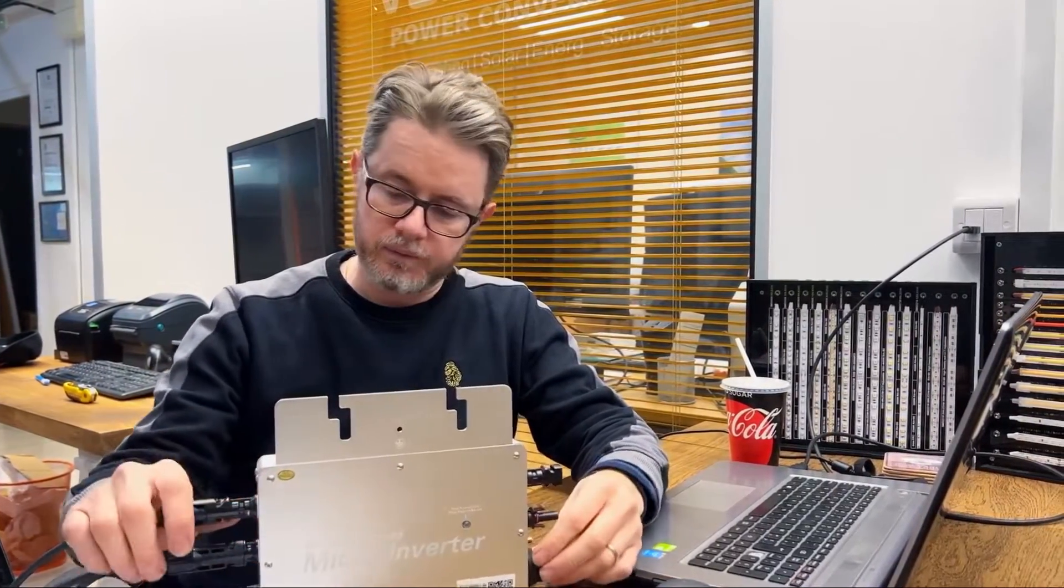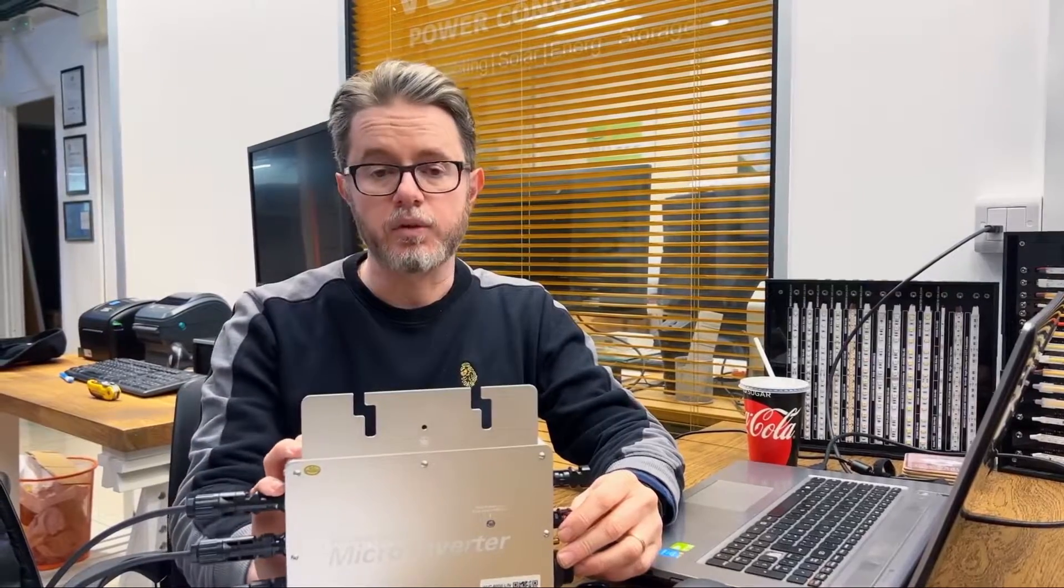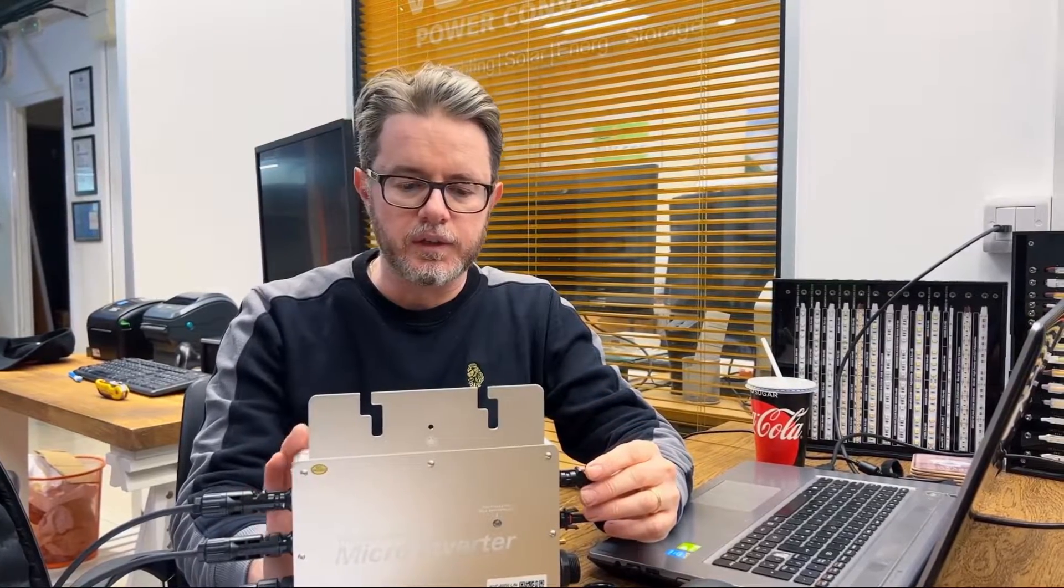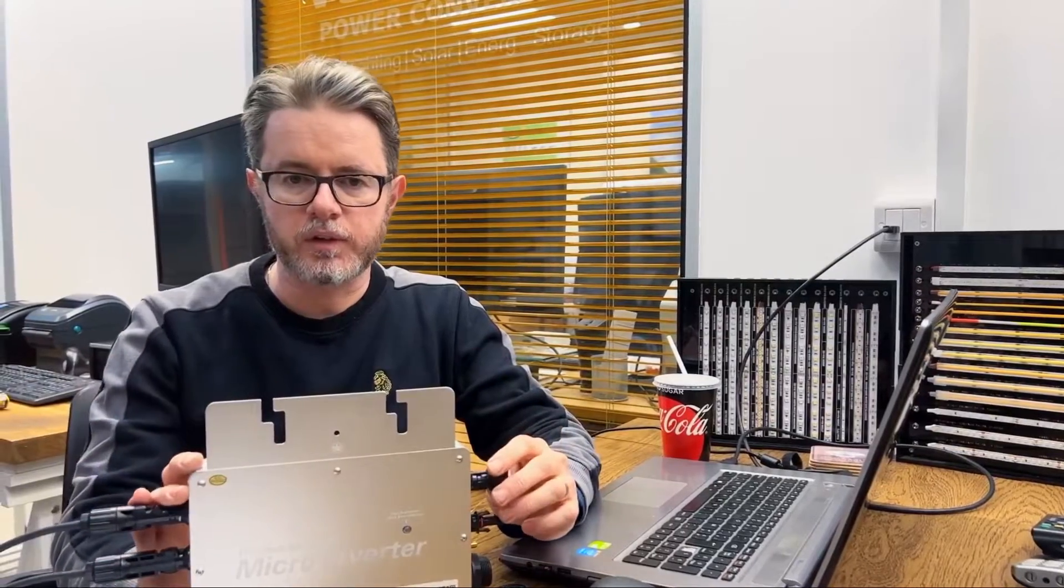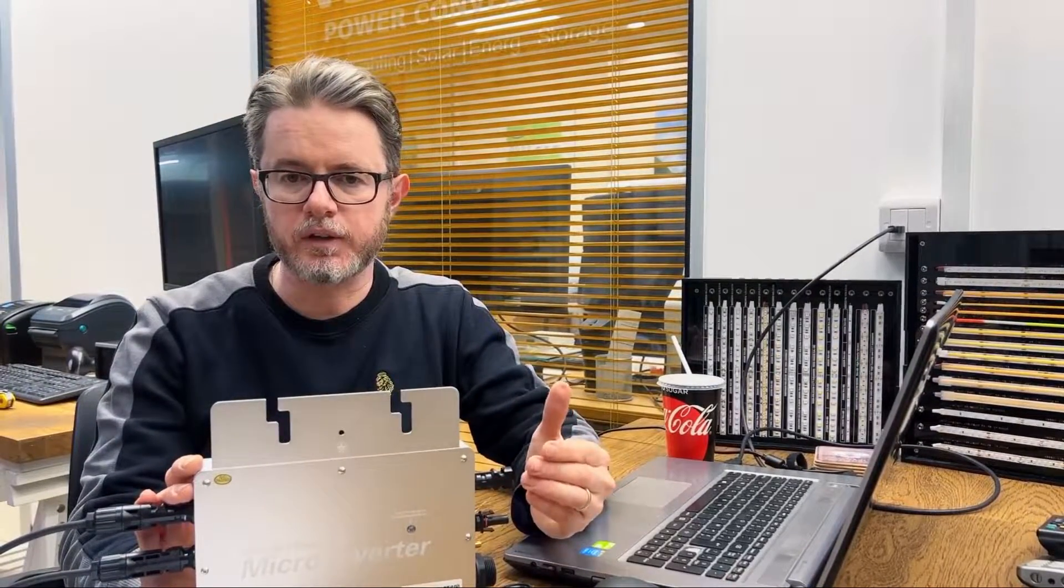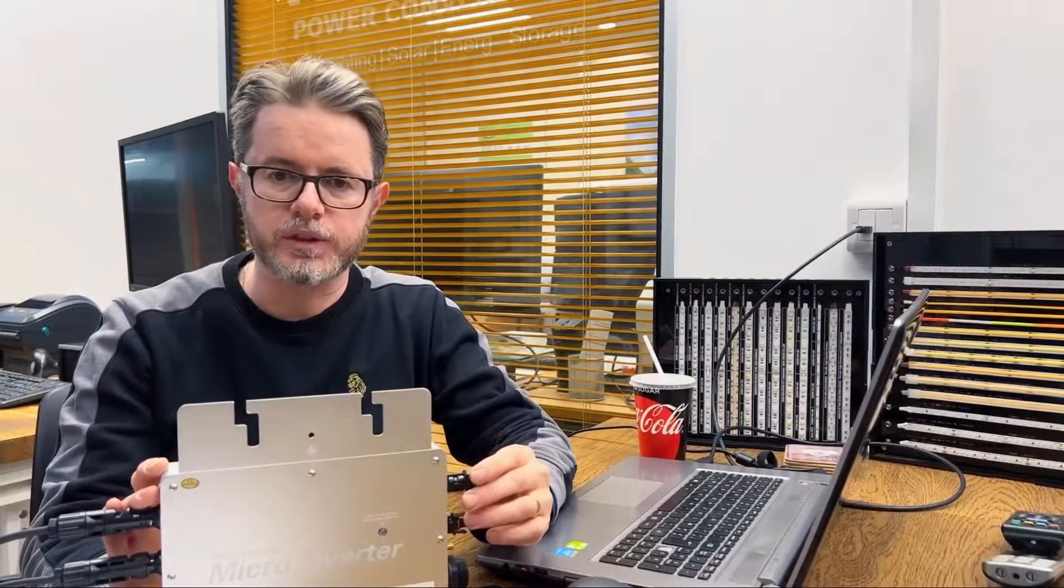Another advantage that we like about micro inverters is the redundancy. You don't have a single point of failure in your system like with string inverters. If a micro inverter fails, you still have another group of micro inverters running and generating electricity. With string inverters, when there is a fault, the whole system goes down.